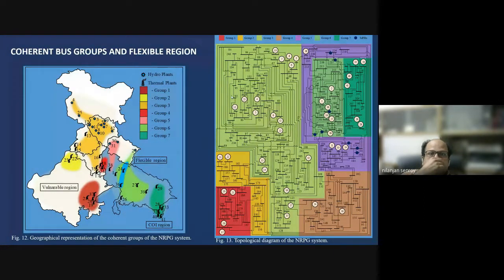So here you can see we have identified 7 groups of generators in the northern grid, and based on the indices that have been calculated group wise, we have identified the most flexible region. This is the most flexible region, central UP. Southeastern UP is the center of inertia, it is the heaviest region. Rajasthan here is one of the most vulnerable regions because of low inertia and low meshing.